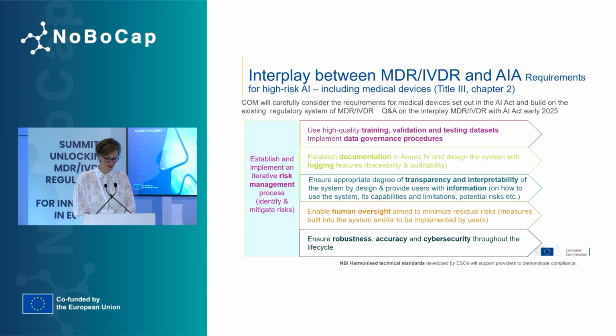So for the medical devices or AI-enabled medical devices, they have to comply with both MDR, IVDR, and the AI Act. And there are, of course, some overlapping requirements like the risk management, technical documentation, conformity assessment procedures, and post-market monitoring. The Commission is looking very carefully at these requirements, and we're also working closely with DG Connect, which is in the lead of this regulation, to try to use the MDR, IVDR regulatory system and incorporate the requirements into the system to avoid duplication.